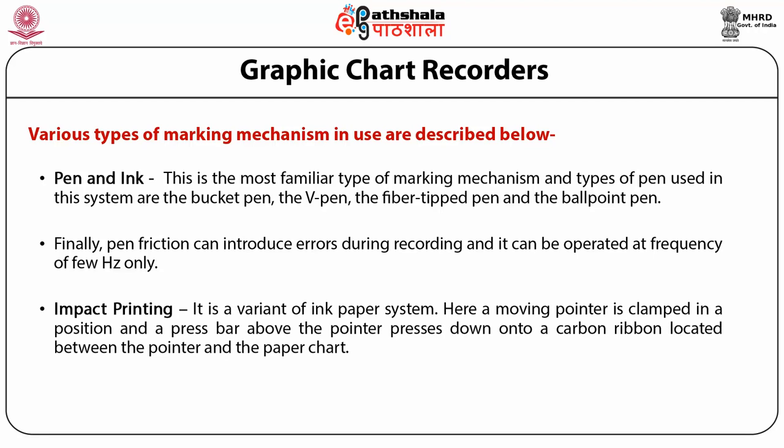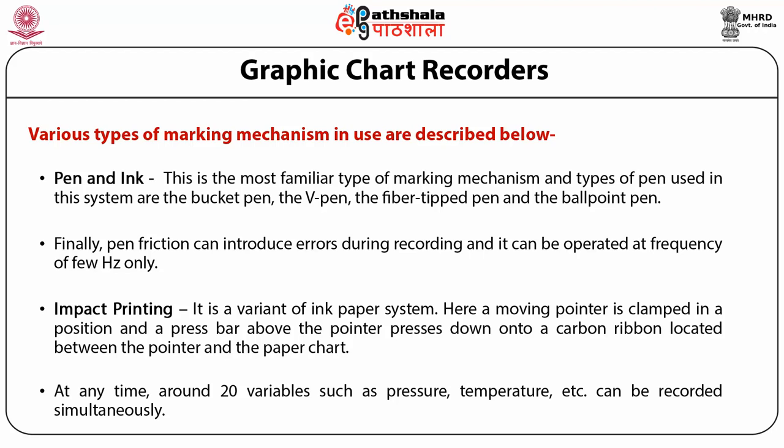B. Impact printing: This is a variant of the ink-paper system. A moving pointer is clamped in position and a press bar above the pointer presses down onto a carbon ribbon located between the pointer and the paper chart. Carbon markings imprinted on the chart serve as a record. Large format recorders with 0.28-meter wide strip charts use impact printing to record data. Around 20 variables such as pressure, temperature, etc. can be recorded simultaneously.